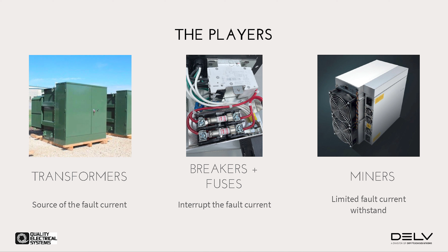So basically, the transformer creates the fault current. You've got circuit breakers or fuses in almost everything that I've seen. Those are what limit the fault current. Fuses are really, really good at limiting fault current because they're much faster than breakers. When you have a short, the fuse can blow so fast that as the current starts to rise, the fuse can blow before you get all the way to the fault current level. This is what they call a let-through curve, and it significantly helps improve the safety in your mining. So with our system, you've got a fuse and a breaker in series to give you maximum protection.